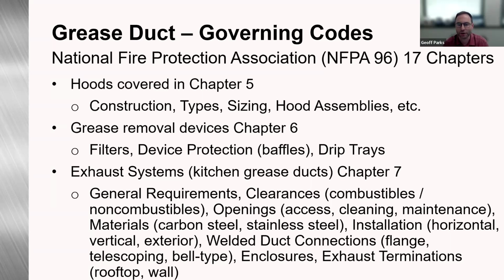Grease removal devices are covered in chapter 6. Any filters, device protection like baffles, drip trays. Chapter 7 covers the exhaust systems, including grease exhaust ductwork. Some of the general requirements are covered: clearances to combustibles, non-combustibles, any openings, access for cleaning, maintenance, the required materials, carbon steel, stainless steel, installation, welded duct connections, flange, telescoping, and bell type.